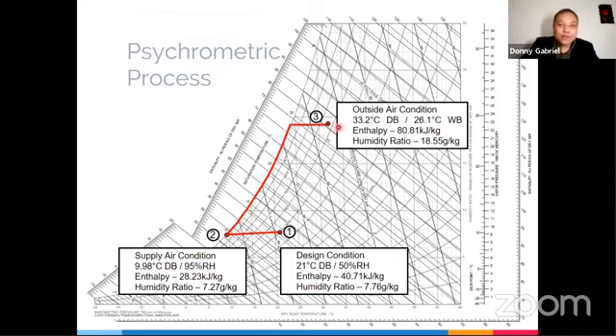All right. Again, what we discussed earlier, the process from outdoor air going to your indoor air is not a straight line. It cools down first, going to the saturation point before it goes down. It's not a straight line from 3 to 2. It's not a straight line from 3 to 1. But it goes cooling first, then after cooling, reaching the saturation point, it dehumidifies. That's why you will get condensation. That's where the water comes from. It dehumidifies. All right?